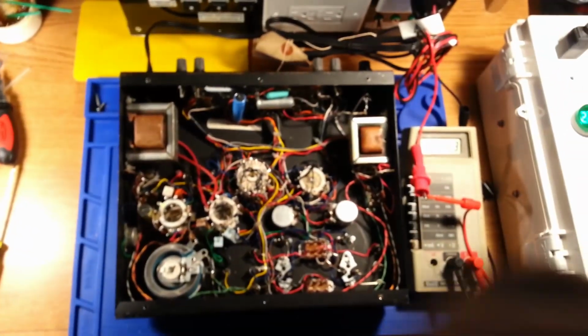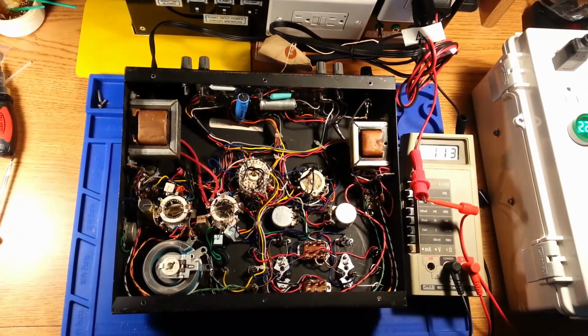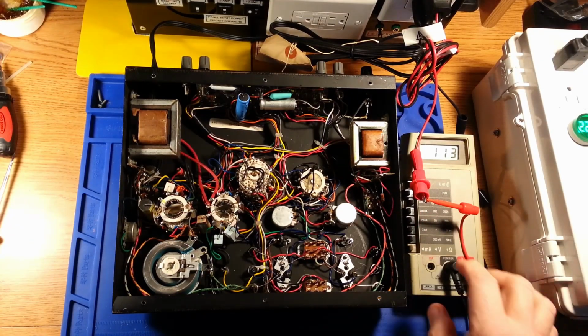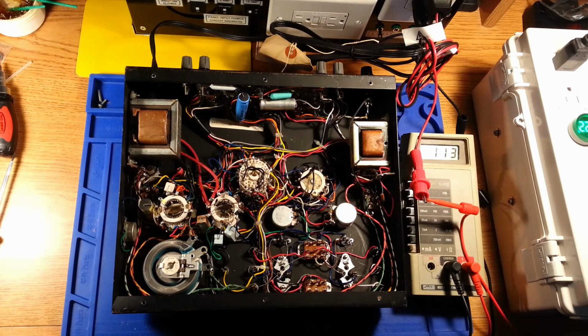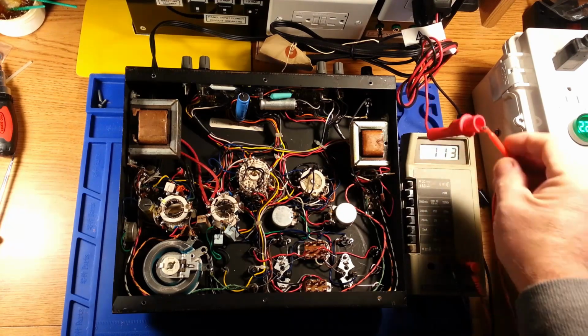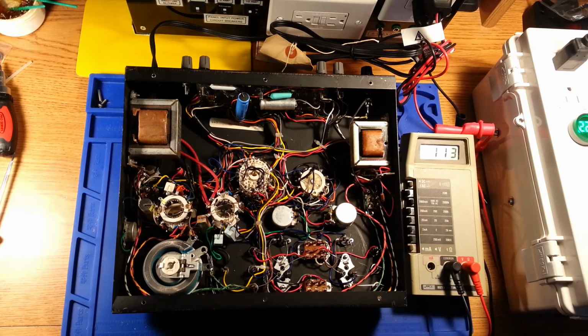Right now I'm going to be running things through the isolation transformer, and I have an old sacrificial meter. I'm using a meter that I don't normally use. It's an older Fluke. It's being used because I'm not sure of the actual AC voltage output of that transformer. It's rated at 1000 volts, but I think that might be the peak voltage, 1000 or 1400 volts. I'm not willing to connect a regular, higher-priced meter to it until I figure out what voltage it might be. If this one overloads, I can possibly go to a meter with a higher rating or introduce a high voltage probe into the testing. But in the meantime, we're going to use this meter.